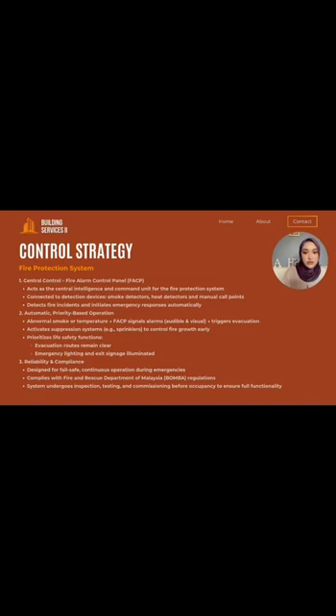Control strategy. For the fire protection system, the control strategy is central control. The Fire Alarm Control Panel (FACP) acts as the central intelligence and command unit for the fire protection system. It is connected to detection devices like smoke detectors, heat detectors, and manual call points. It detects fire incidents to initiate emergency response automatically.